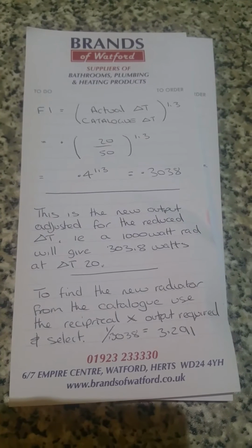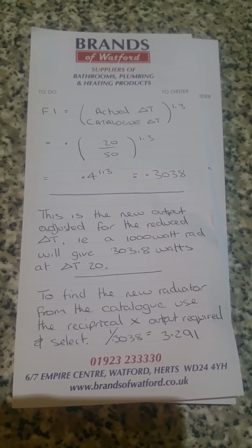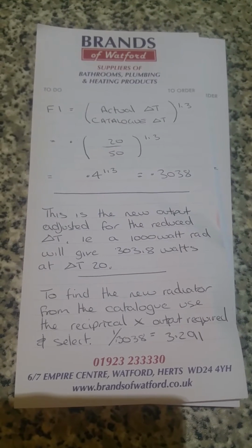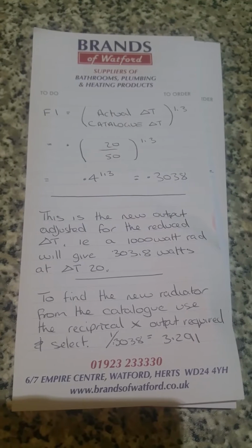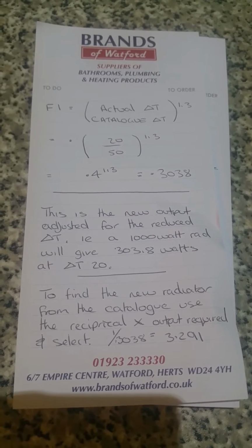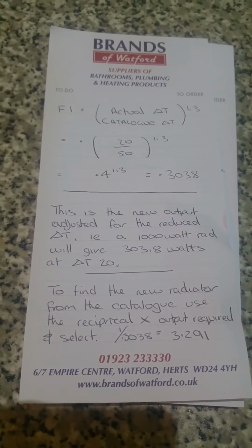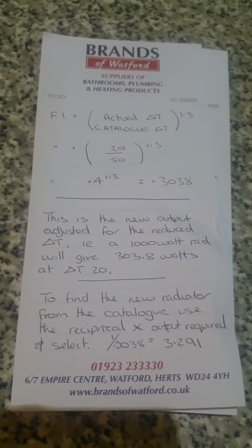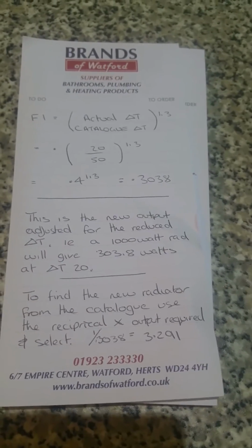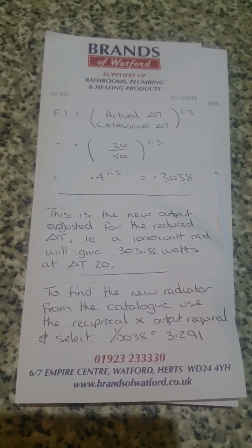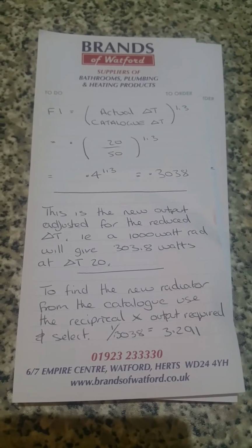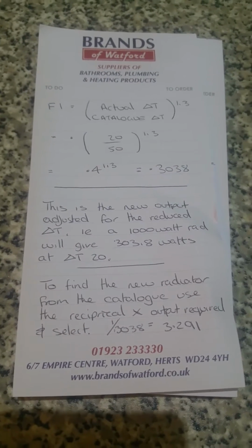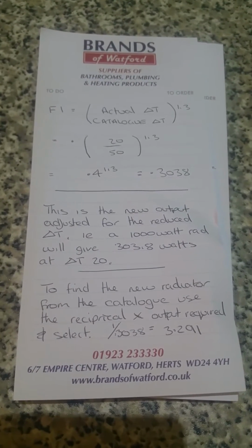Radiator sizing. Normally when we select a radiator from a chart, the standard is for a delta T50, that's a 50-degree difference between the average surface temperature of the radiator and the desired room temperature. And normally think of this in terms of an average radiator temperature of 70 degrees and a room temperature of 20.